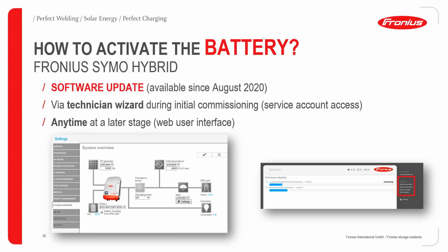If you have an existing customer who has had this Symo Hybrid for 2 to 3 years already, please do a software update in advance. Since August 2020, we are fully compatible with the new BYD Battery-Box HV. Just connect via the Wi-Fi access point to the inverter interface and look under system overview to find the battery. If the wiring is done correctly, the battery should be detected automatically with an SOC value of 93%. Then save it, don't forget that part.